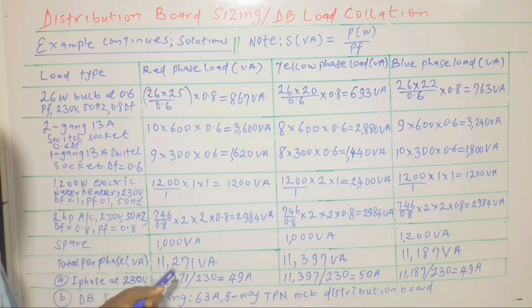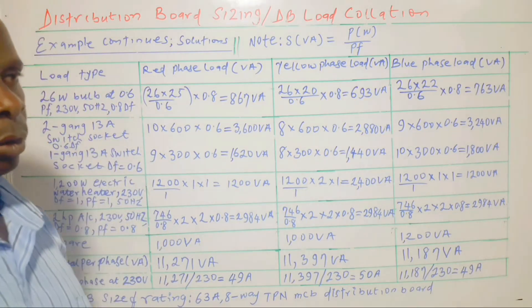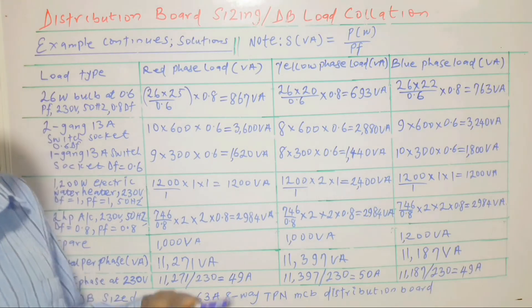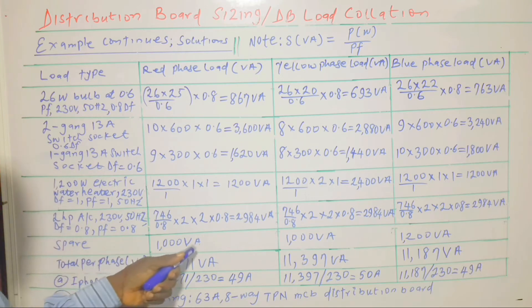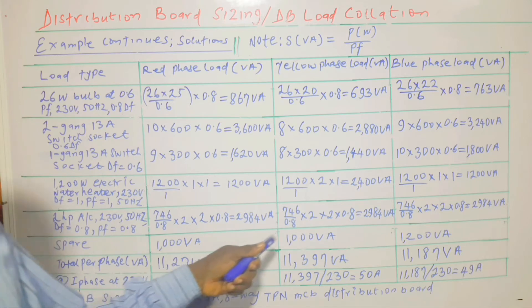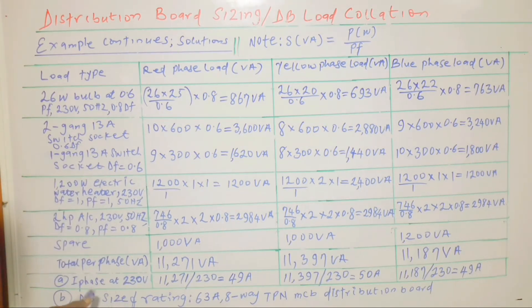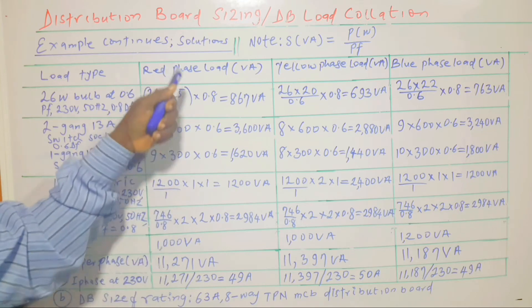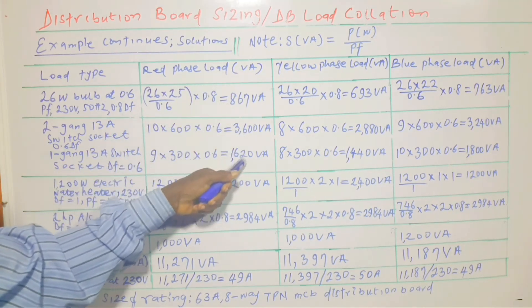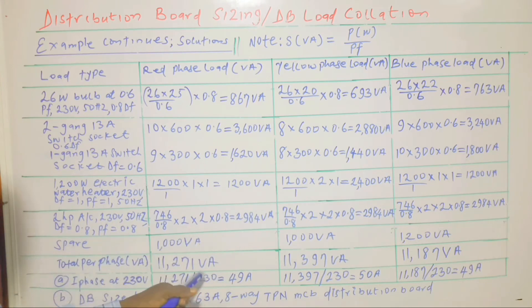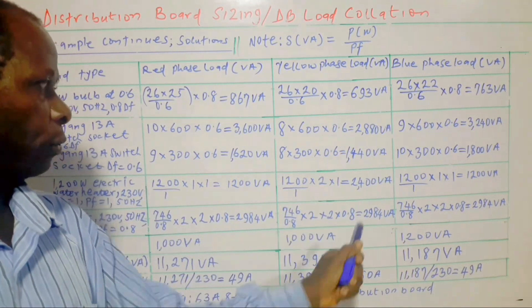We also need to provide spare capacity in case the building users want to connect additional loads in the future — or even immediately after project completion. So we are providing 1,000 VA spare on one phase, 1,000 VA on another, and 1,200 VA on the third phase. The total VA per phase is calculated by adding together all the individual load contributions on each phase, giving the totals for the red, yellow, and blue phases.